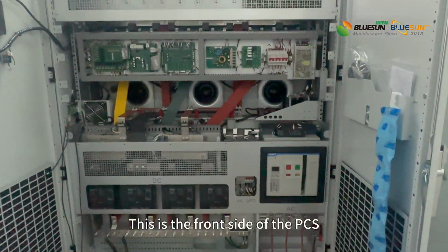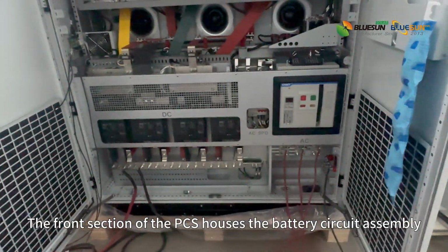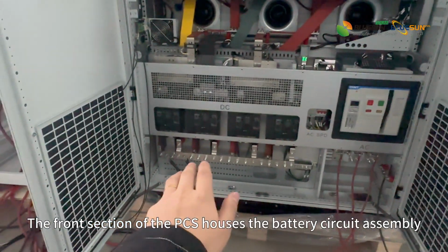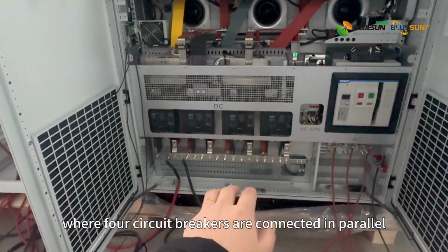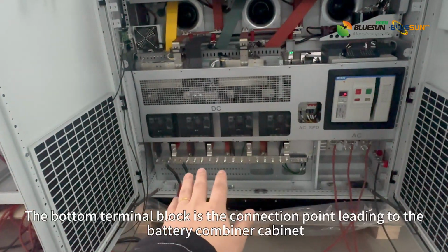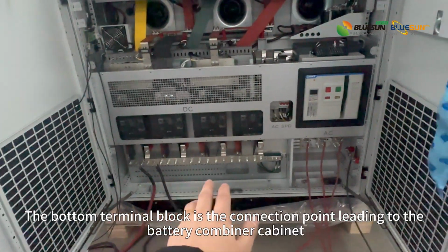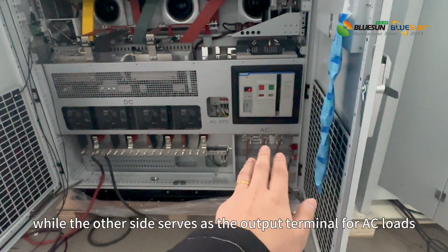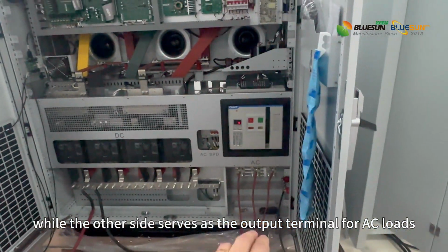This is the front side of the PCS. The front section of the PCS houses the battery circuit assembly, where 4 circuit breakers are connected in parallel. The bottom terminal block is the connection point leading to the battery combiner cabinet, while the other side serves as the output terminal for AC loads.